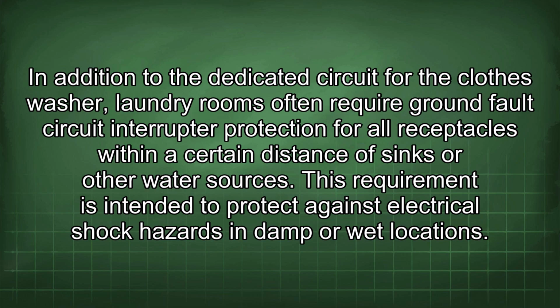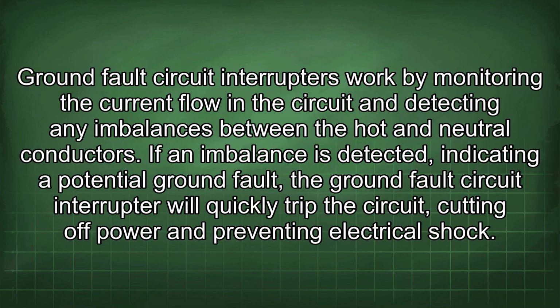In addition to the dedicated circuit for the clothes washer, laundry rooms often require ground fault circuit interrupter protection for all receptacles within a certain distance of sinks or other water sources. This requirement is intended to protect against electrical shock hazards in damp or wet locations. Ground fault circuit interrupters work by monitoring the current flow in the circuit and detecting any imbalances between the hot and neutral conductors. If an imbalance is detected, indicating a potential ground fault, the ground fault circuit interrupter will quickly trip the circuit, cutting off power and preventing electrical shock.